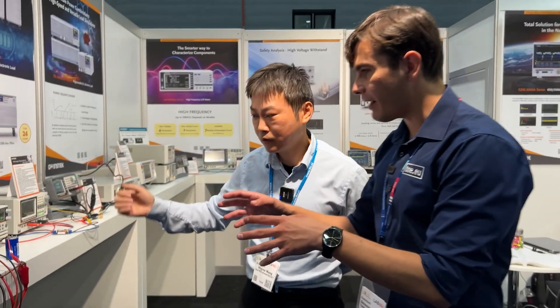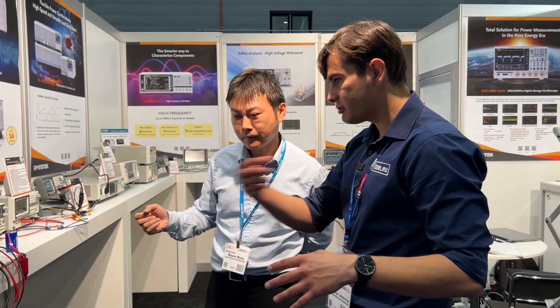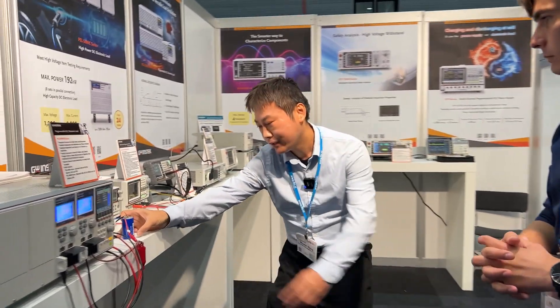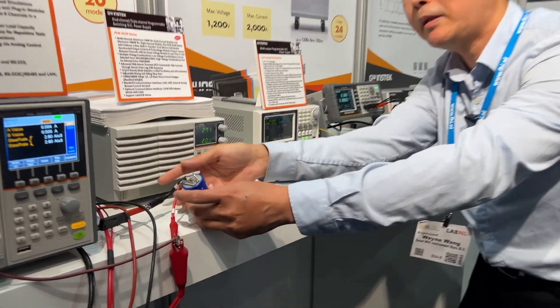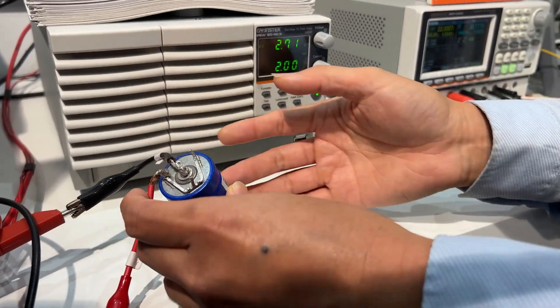You can also use this with different types of batteries — you can select the charge rate, discharge rate, voltages, and currents you want to test. Yes, exactly — for any battery where charging and discharging is allowed. Here you can see the supercapacitor spec is 2.7 volts, so we set 2.7 volts for the charge.